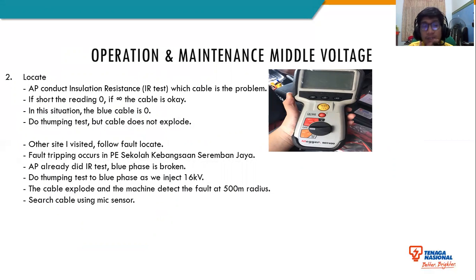Therefore, that's why it is less explode. From the other side, I visit and follow the fault locate. The fault tripping occurs in the PE. I already did an IR test, so we know that the blue phase is broken. We do a thumping test on the blue phase as we inject 16 kV. The cable explodes and we detect it with the machine at the fault locate van at a 500 meter radius.